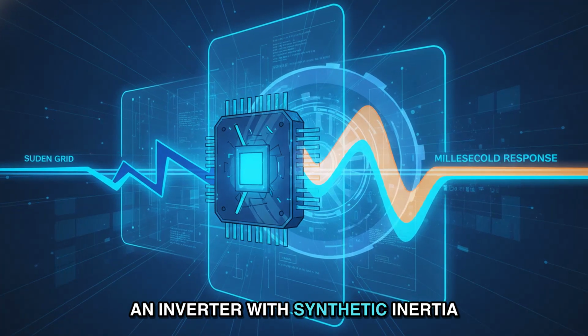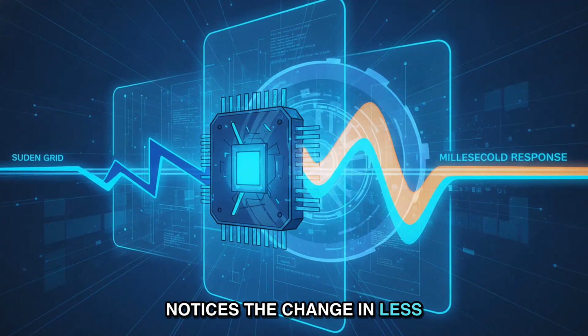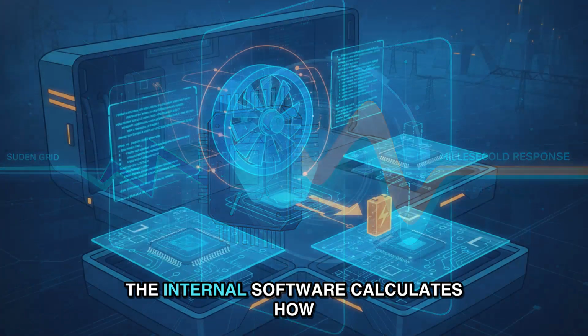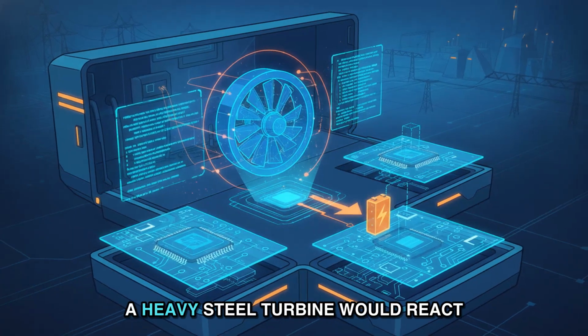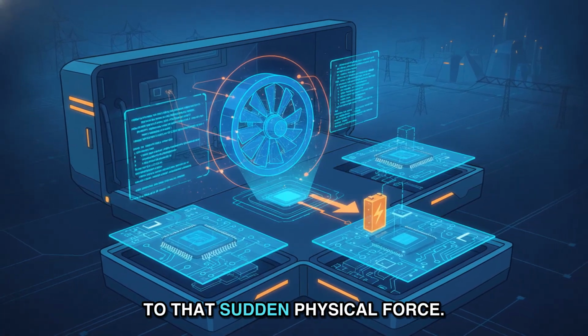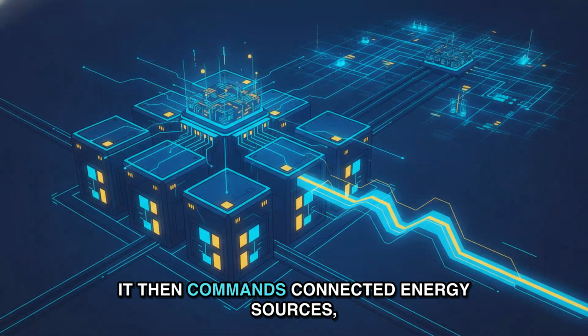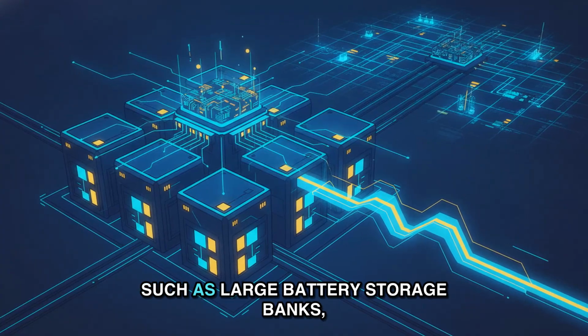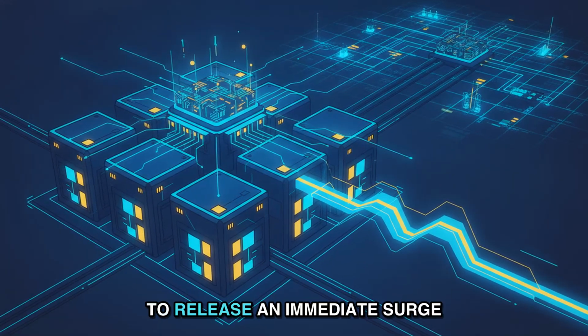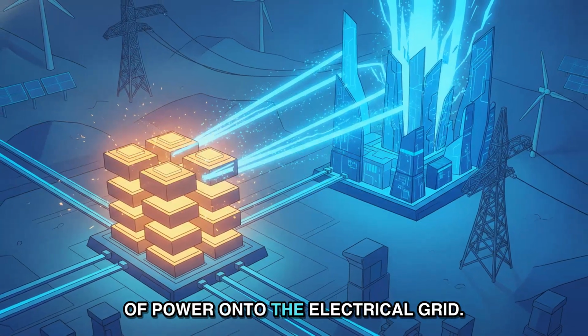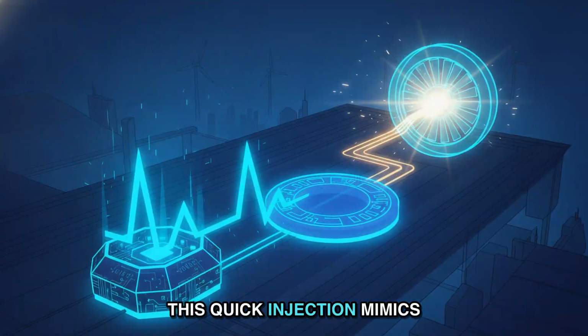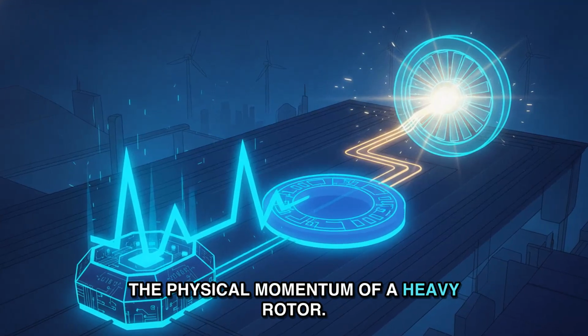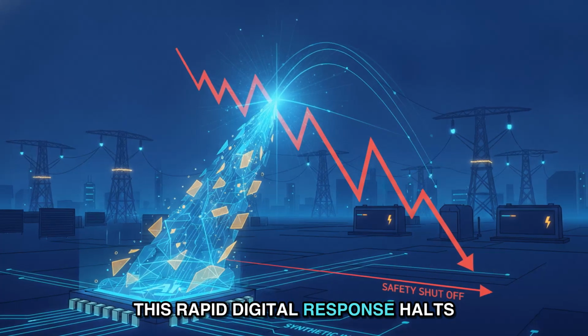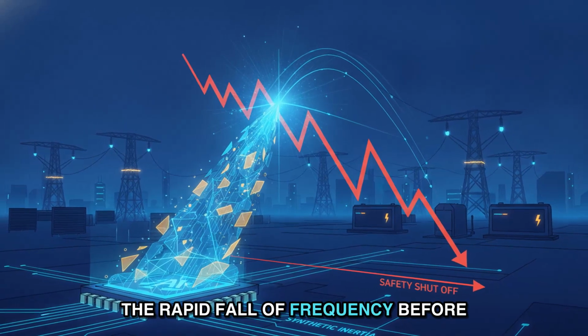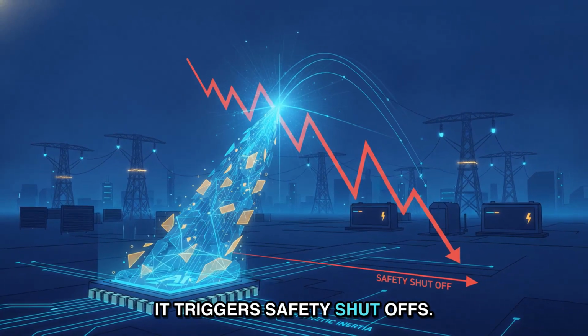When the grid frequency drops suddenly, an inverter with synthetic inertia notices the change in less than a single millisecond. The internal software calculates how a heavy steel turbine would react to that sudden physical force. It then commands connected energy sources, such as large battery storage banks, to release an immediate surge of power onto the electrical grid. This quick injection mimics the physical momentum of a heavy rotor. This rapid digital response halts the rapid fall of frequency before it triggers safety shutoffs.